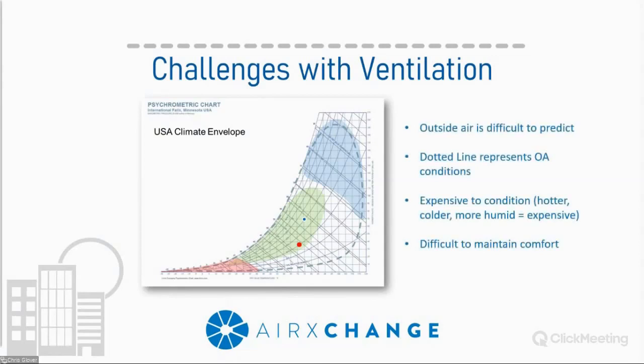Looking at the psychrometric chart on the left, what you're seeing in that dotted line is what your outside air conditions could be on any given day at any point in the country. That's a pretty big operational window. The red dot and the blue dot represent your typical indoor air conditions in both heating and cooling modes. As you move away from those points, the bigger the energy load is going to be on the building. Essentially, the hotter it gets, the colder it gets, the more humid it gets, the more energy you're going to use to condition that air to a point that's acceptable for the space. Also, because you have this big operational window, designing a system that can operate efficiently with all these conditions in place can be quite difficult.